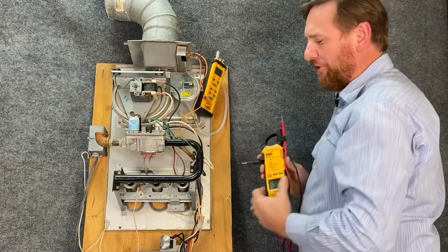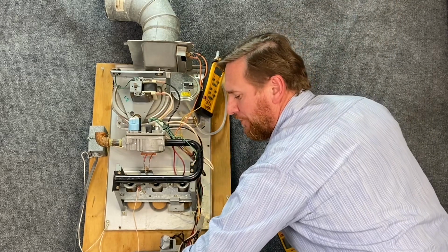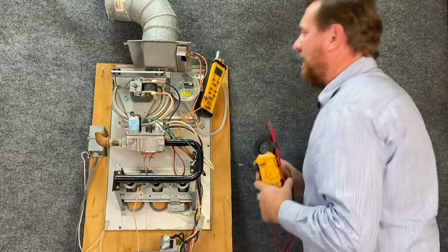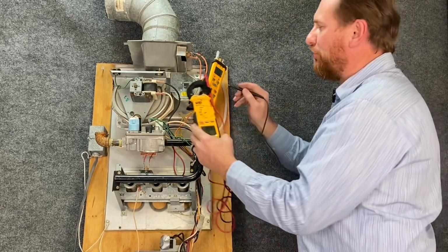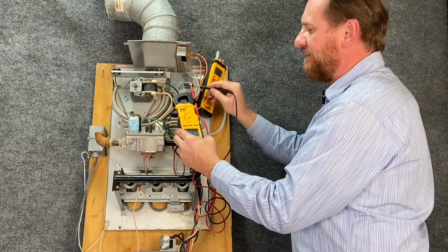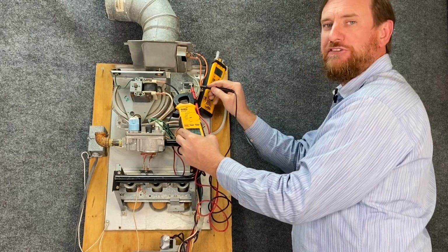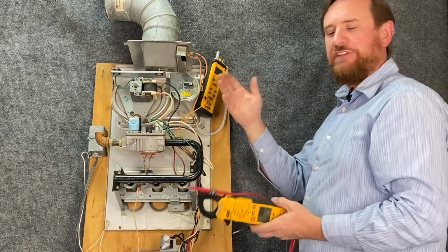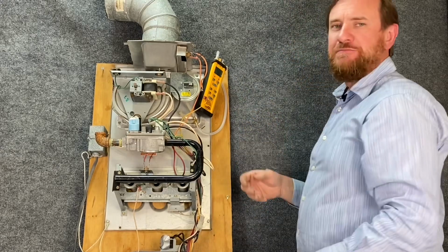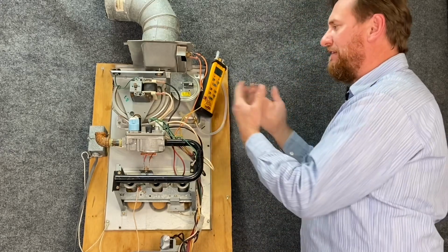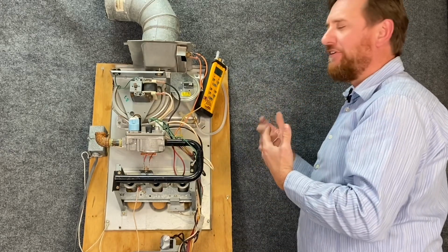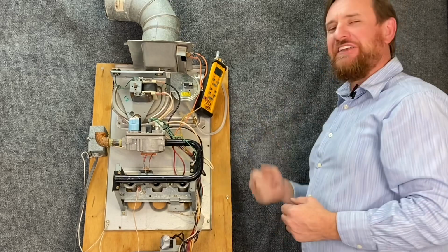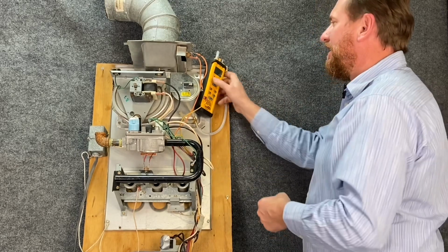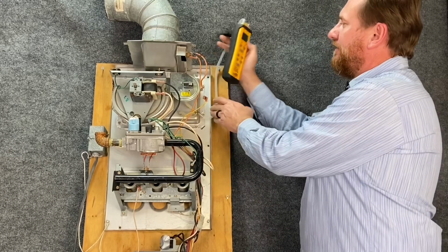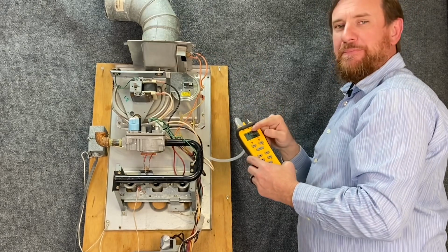My switch is closed. If I shut my fan motor off, I lose my vacuum, the switch will open. So if we check the resistance now, we show OL, the switch is open. Two different ways of checking the switch. I prefer the voltage method because it's faster. I don't have to pull wires loose or worry about wire connections going bad. There is a third way of checking this. This particular model of manometer has a pump built into it.